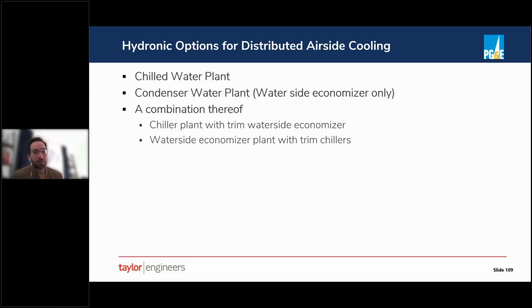And in other cases, we will have a waterside economizer system that then has what we call trim chiller capacity, because that means that, say, on a design day, we can do 50% of the load still with the economizer. Then we can do the other 50% with the chillers, and the chillers don't need to be sized for the full load data center.